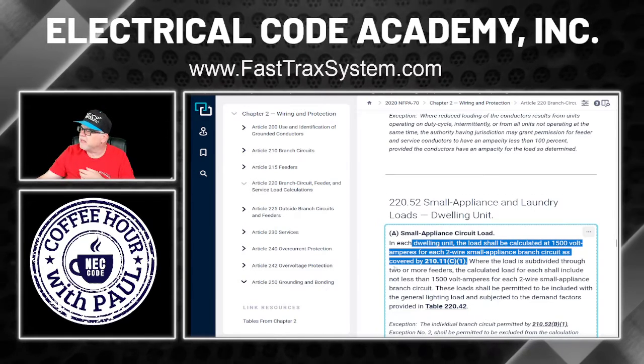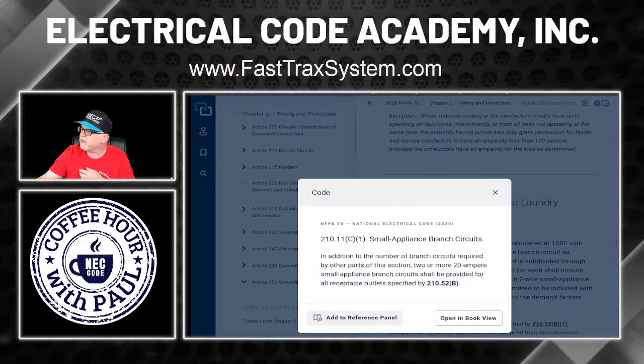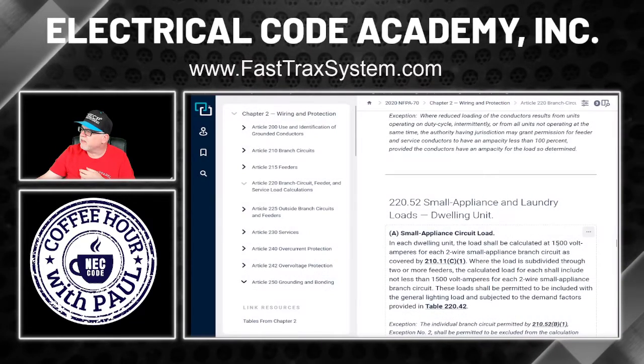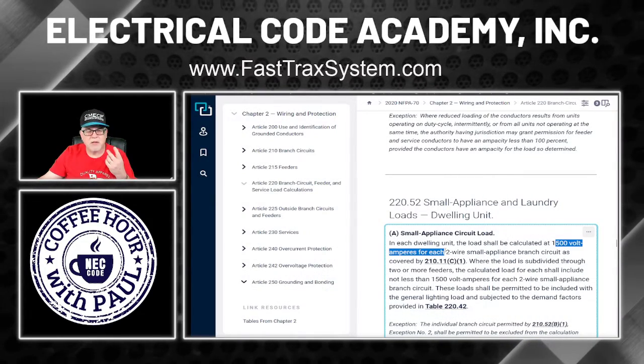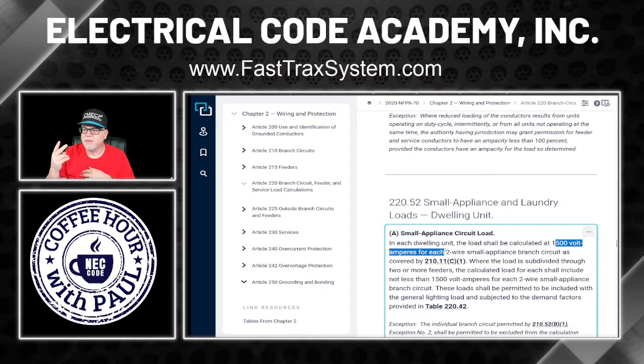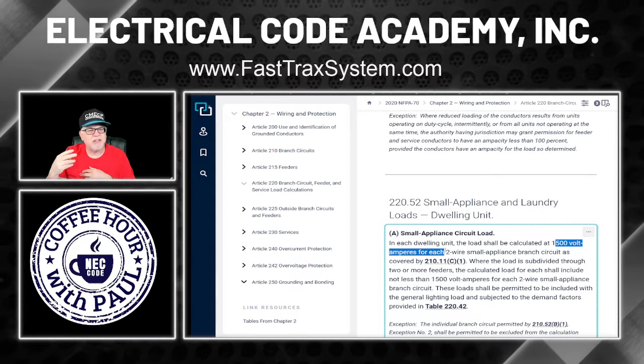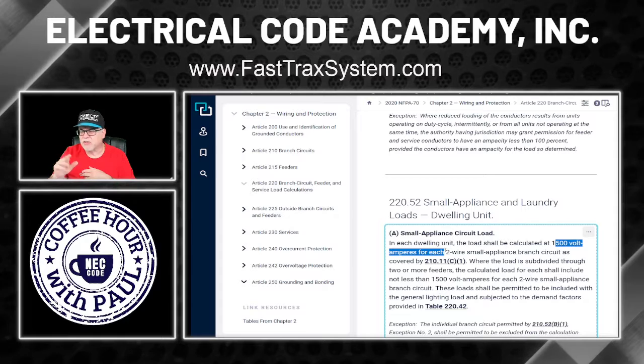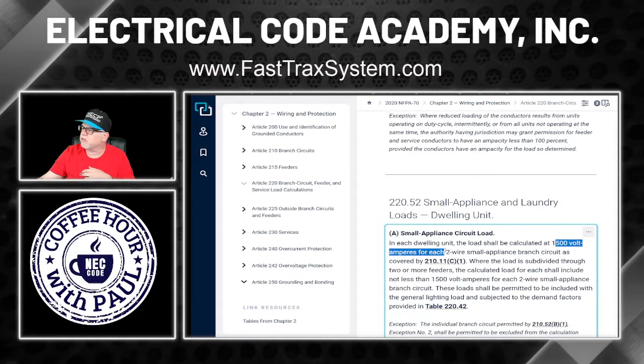And it tells me that they are what? 1,500 VA each, right? So we have to have a minimum of 2. So that's 1,500 for this. That's 3,000 right there just for the two 1,500 small appliance branch circuits, okay?